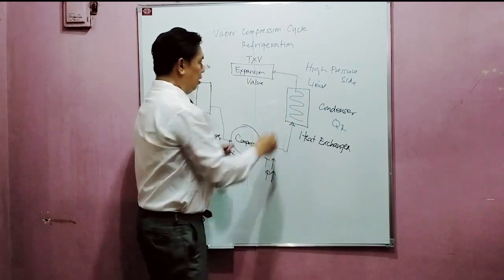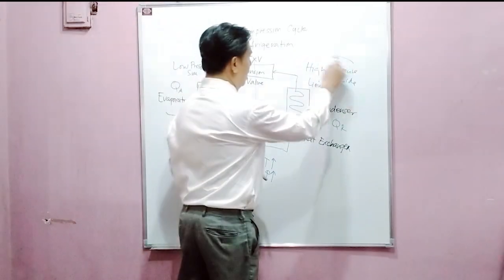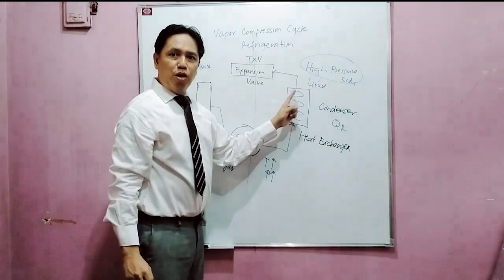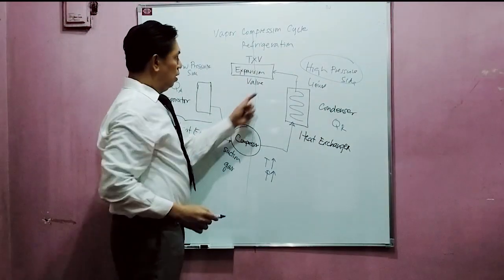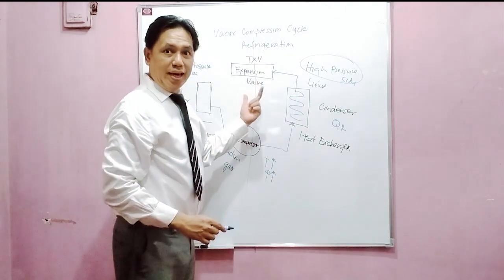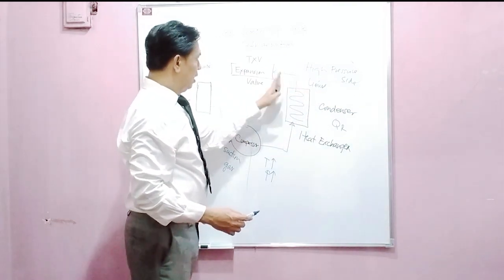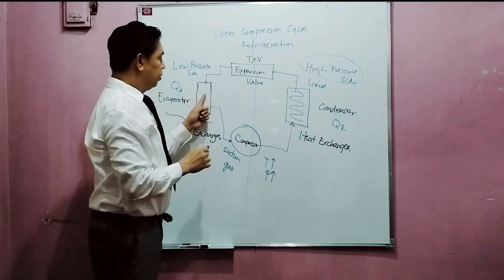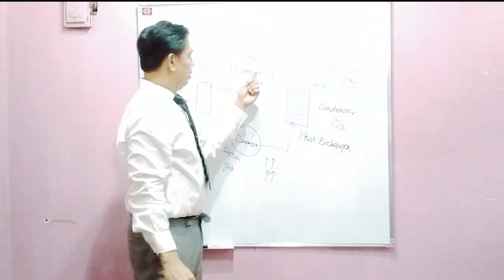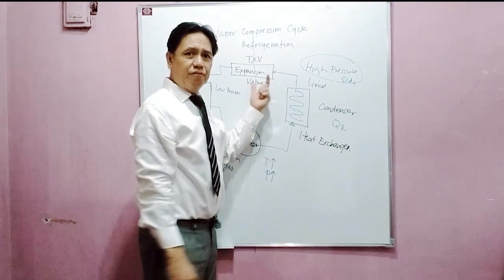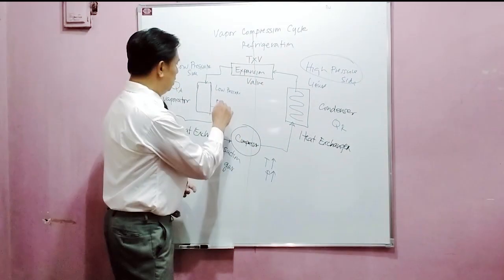Then it goes into the expansion valve. This side is still high pressure — the liquid form of refrigerant here is high pressure — so it goes into the expansion valve. The function of the expansion valve is to lower the pressure of the liquid refrigerant, so that when it goes to the evaporator it will have a low pressure. The thermal expansion valve has a series of orifices, so when the refrigerant passes through, it lowers the pressure and lowers the temperature.